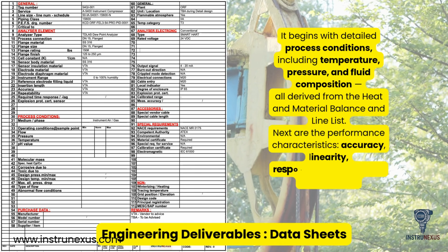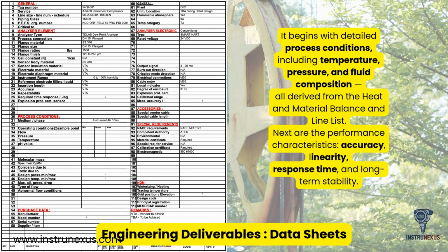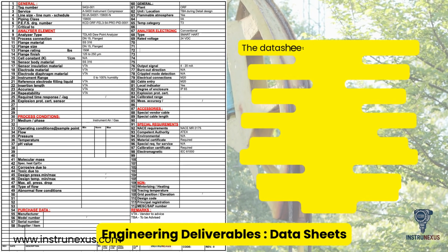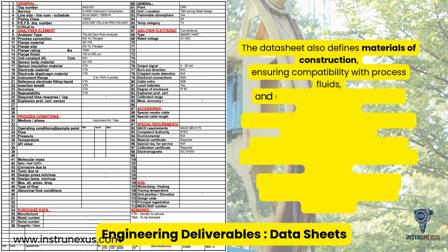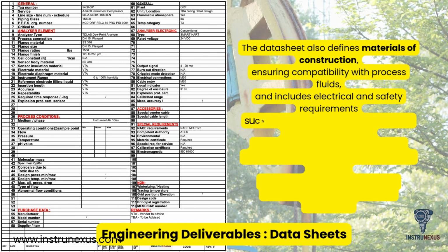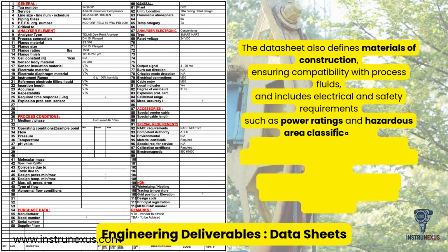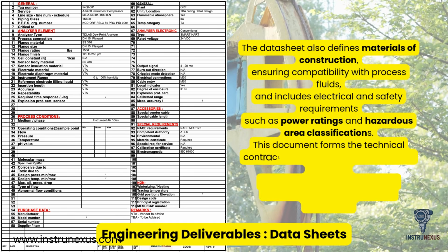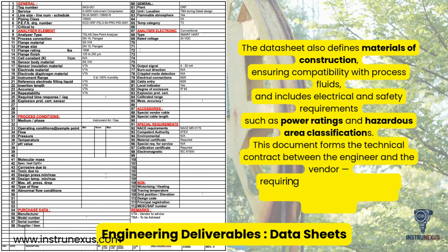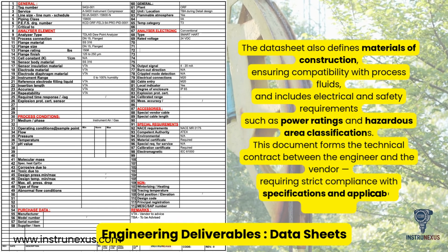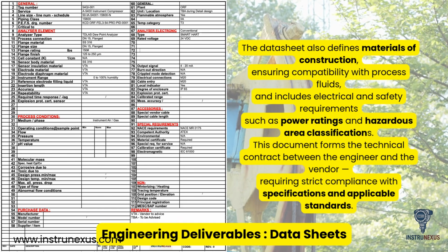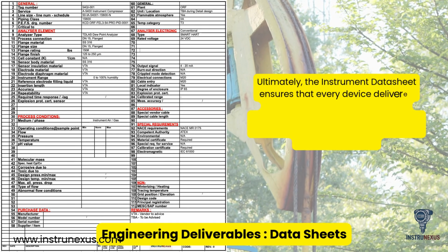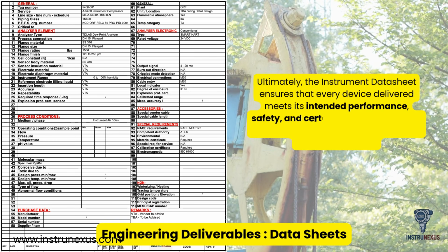Next are the performance characteristics: accuracy, linearity, response time, and long-term stability. The datasheet also defines materials of construction, ensuring compatibility with process fluids, and includes electrical and safety requirements such as power ratings and hazardous area classifications. This document forms the technical contract between the engineer and the vendor, requiring strict compliance with specifications and applicable standards. Ultimately, the instrument datasheet ensures that every device delivered meets its intended performance, safety, and certification requirements, verified through rigorous engineering review and testing.